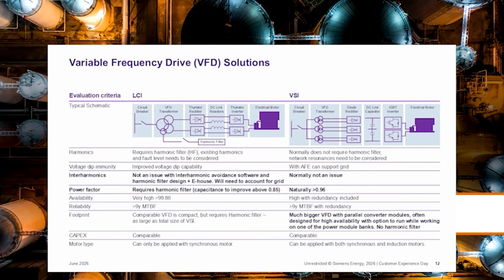And I could talk a long time about this, so I won't, but happy to give these slides to anyone that would like. That current source inverter versus the voltage source inverter, that's the big question if you're going to go with the VFD style of process control. And both have some pluses and minuses. Overall, you're looking at a similar overall footprint when you include the e-house and harmonic filters of an LCI drive versus not having all of those on a VSI drive, but typically more power modules for those inverter requirements when you're converting the waveform back to the speed for the motor.